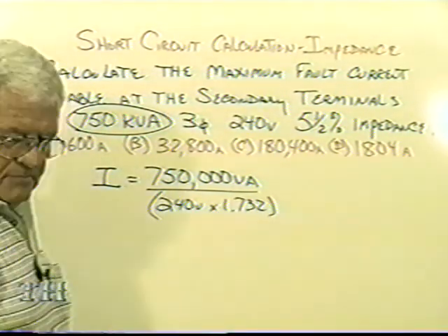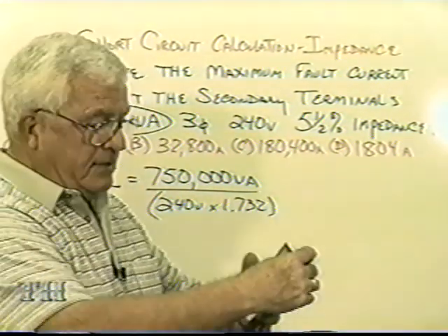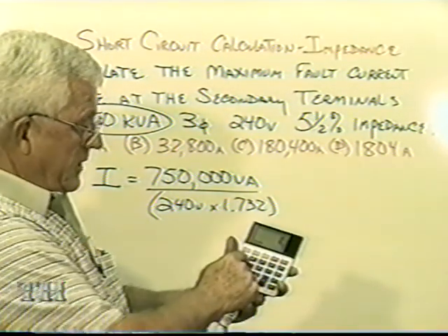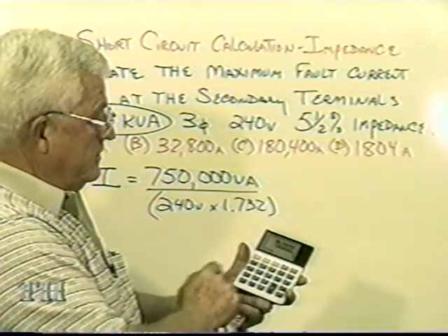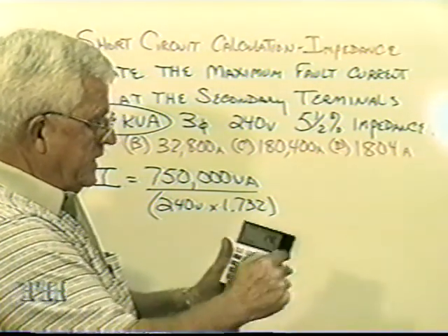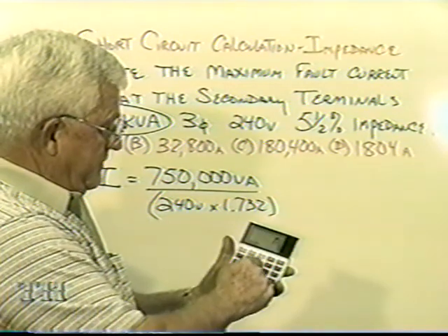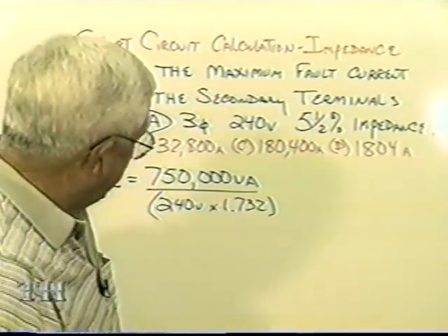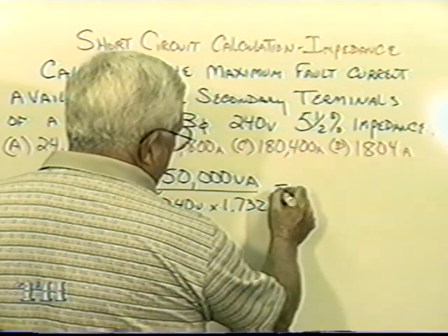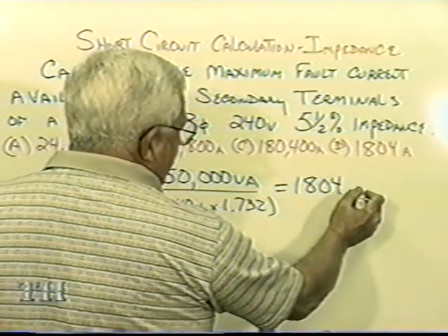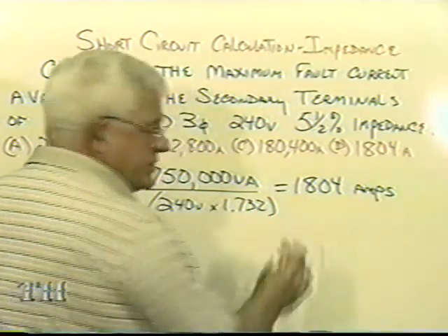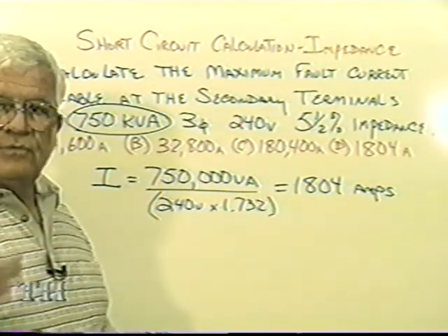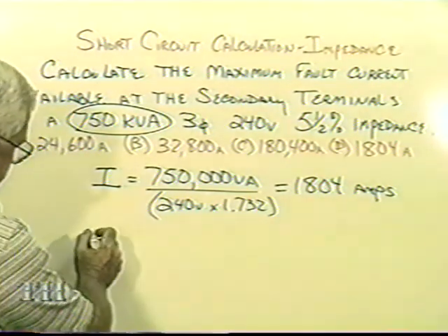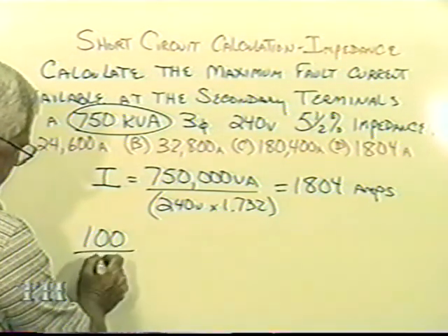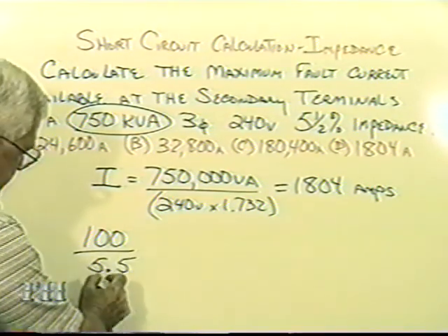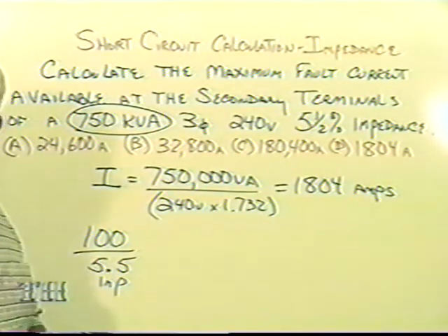And as I've said before on these videos, just take your calculator, clear it, get it on 0. 750,000 divided by 240, hit the divide button, 1.732 equals 1804. That is what we call your rated amps. That's where you start. Now, all you have to do when they give you an impedance, whatever that impedance is, just divide it into 100. Just take the 5.5, the impedance, divide it into the 100. What's the 100? The 100%.